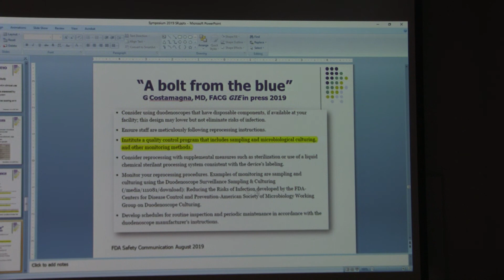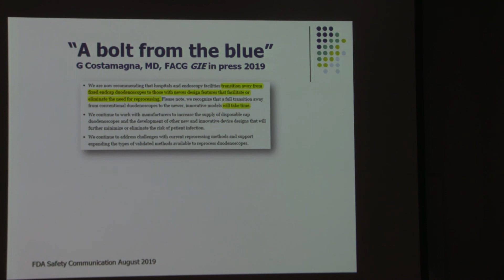The issue is we're in a difficult situation with ATP testing. I'm glad you brought it up. I would recommend you look at the safety communication from the FDA. They specifically said in it that, as of right now, there is not sufficient data on the use of ATP as a check for quality of duodenoscope cleaning. That's why they recommended that the ATP manufacturers evaluate and present post-marketing studies. Until that is done, our institution uses it. I think it's a good thing to continue to use it, but we have to realize that we do not have data to support its use as of right now. I'm pretty sure it will be coming shortly, but that's where we are.